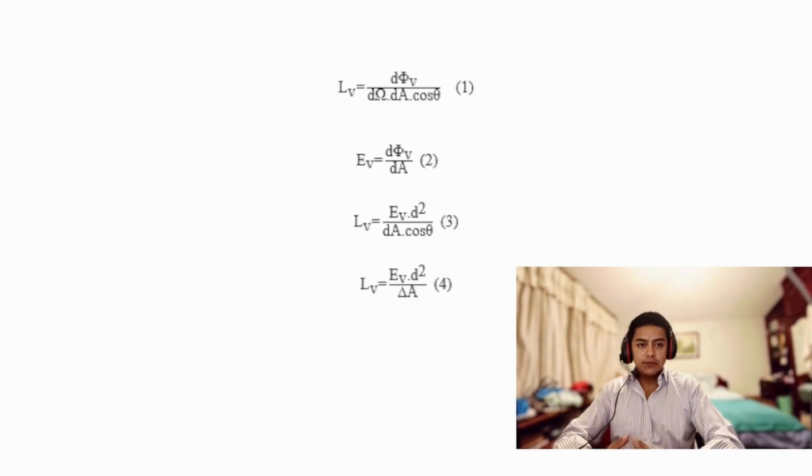If it can be ensured that the luminance remains constant within the surface elements, equations 1 and 2 can be combined, as given by equation 3, where d is the distance between the source and the detector, ensuring correct alignment. It can be considered that the angle between the source tends to 0, as well as that the distance is considerably greater. With this, we get equation 4. Equation 4 is used in practice for the calibration of luminance meters, considering the surface is uniformly illuminated.